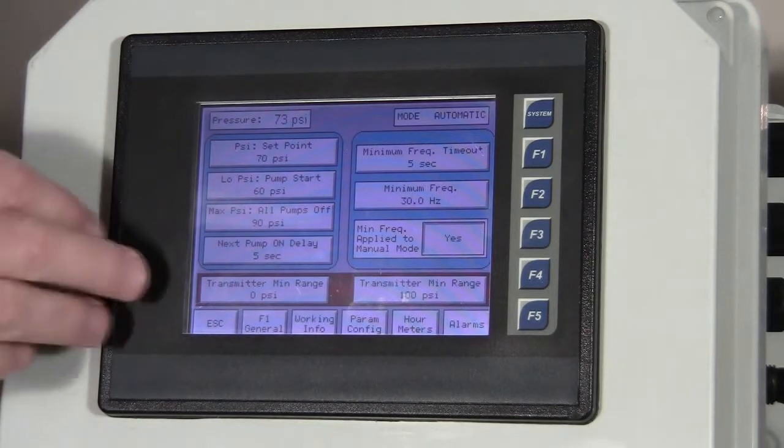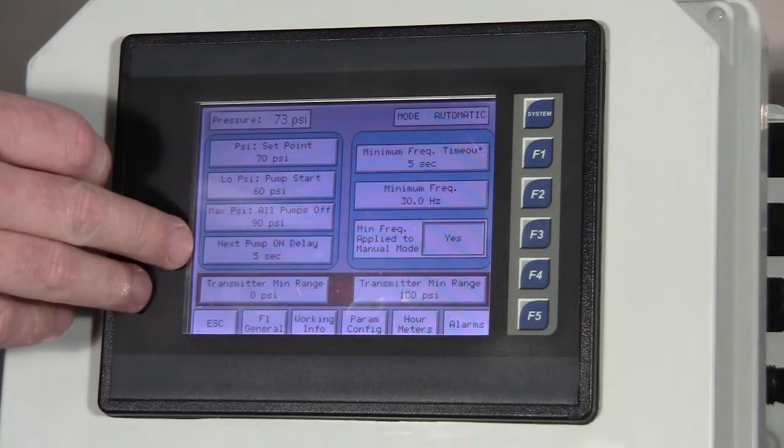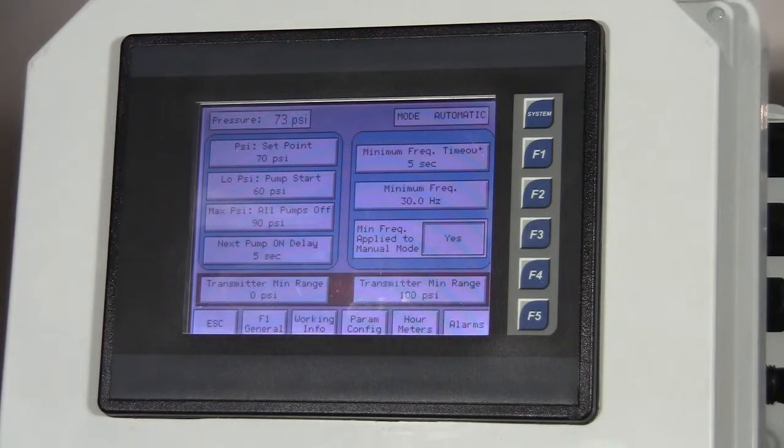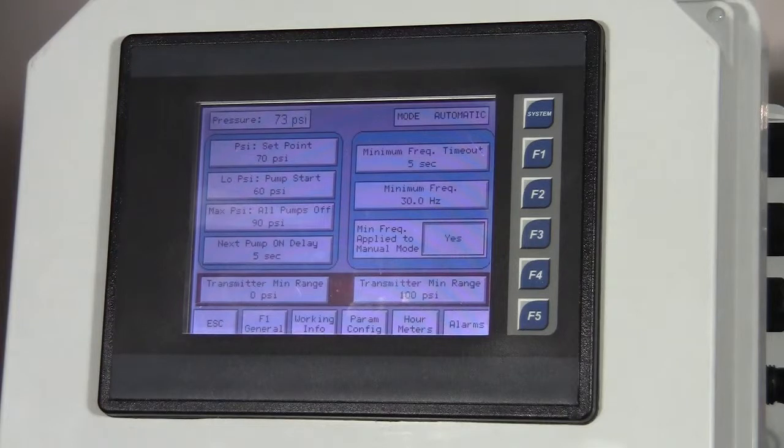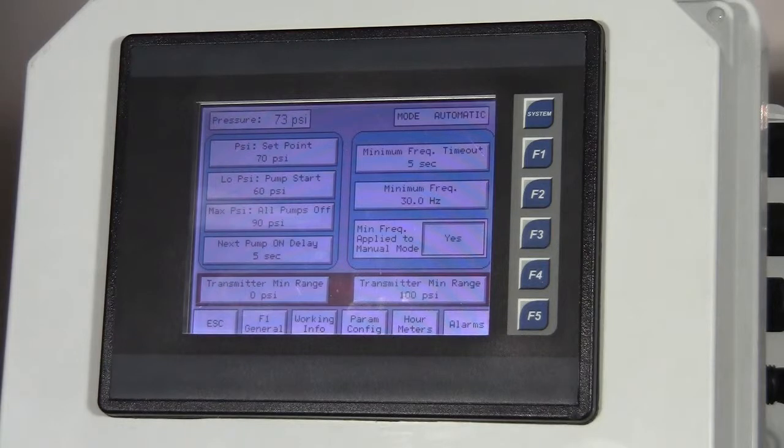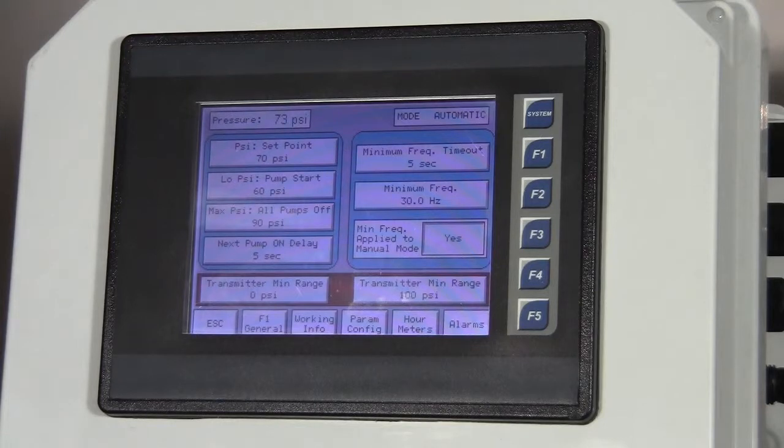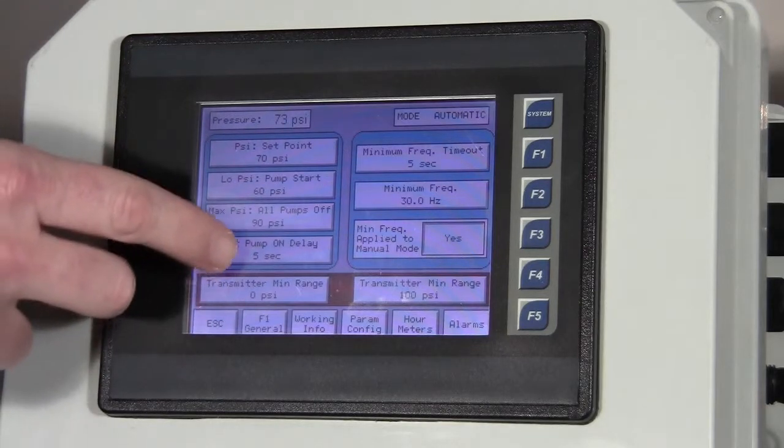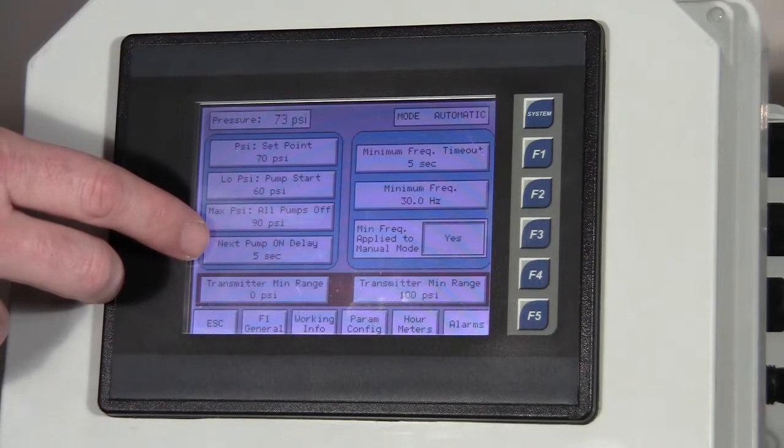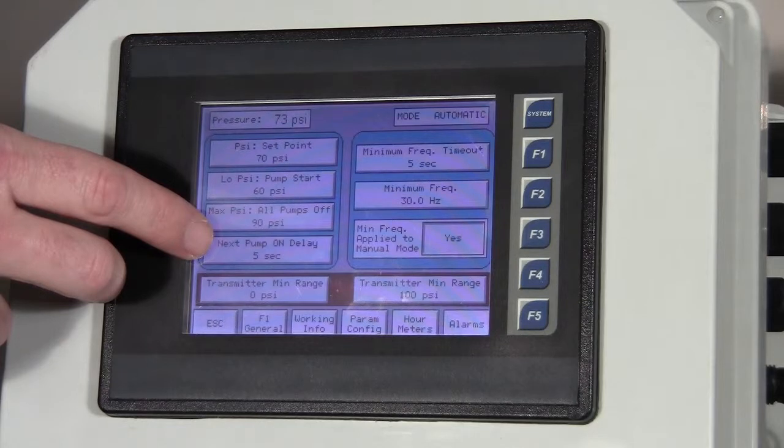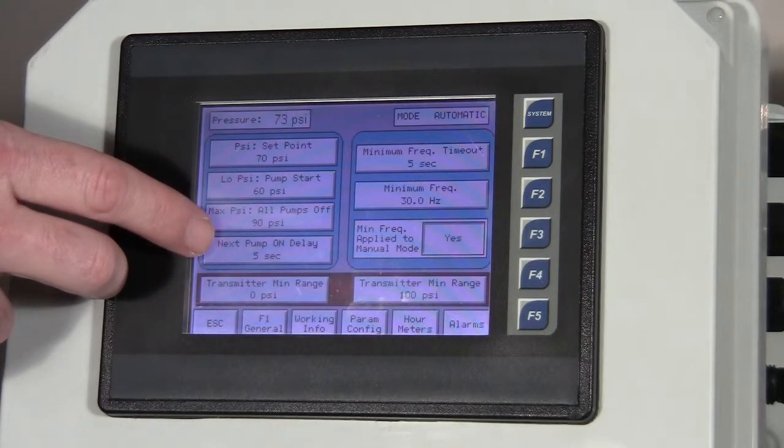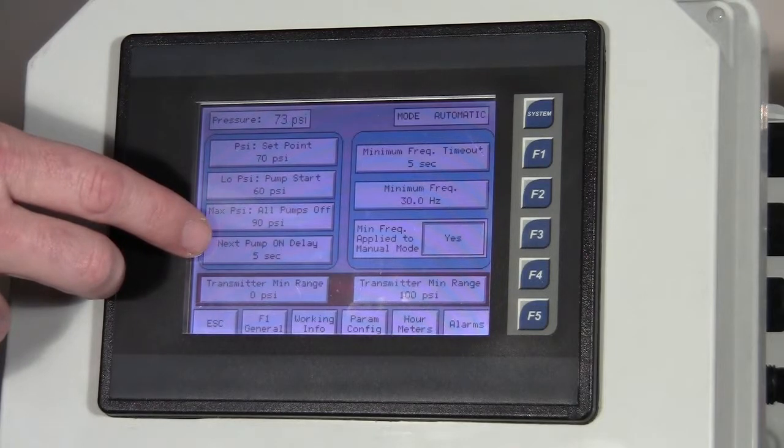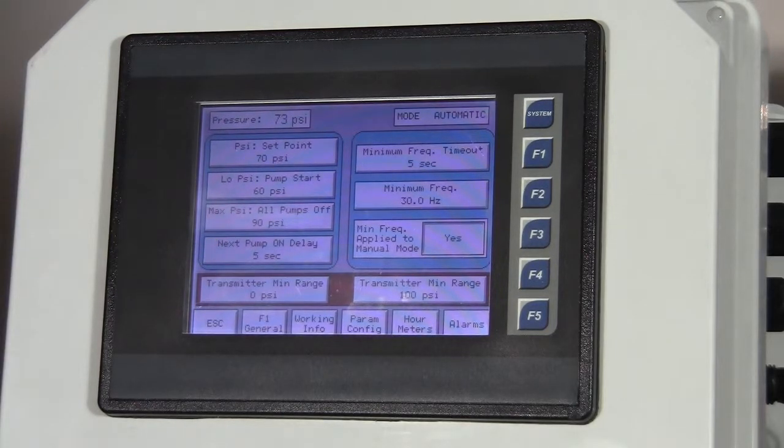And then finally, on this side, we have the next pump on delay. The pumps will come on one at a time. They'll run to maintain the system. But if a particular pump runs at its maximum frequency for a certain amount of time, then it calls for another additional pump to come on. And this is that setting for the delay. So if pump one comes on, pump one keeps ramping up, the pressure keeps going down, it comes up to its maximum frequency, and it stays at that maximum frequency for five seconds, then it calls for an additional pump to come on.